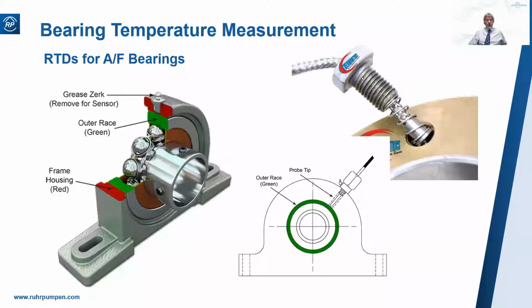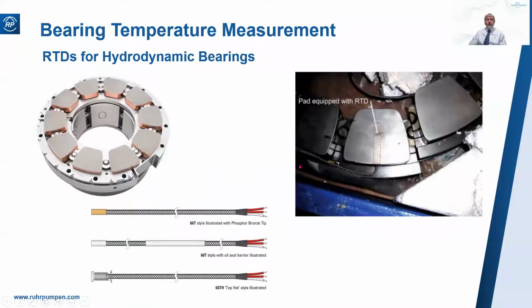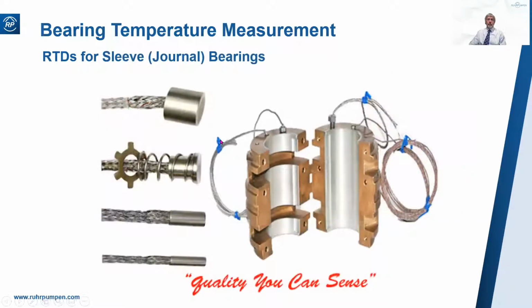So we looked at vibration, now temperature. For anti-friction bearings, the RTD will be spring-loaded so that it rests lightly against the outer race of the ball bearing, like this. For tilting pad bearings, the RTD will be embedded in usually 2 of the tilting pads. And in sleeve or journal bearings, again, embedded in the material. Probably that type, with a spring clip to hold it in place.